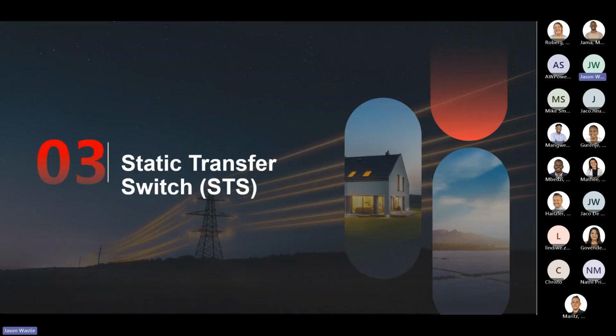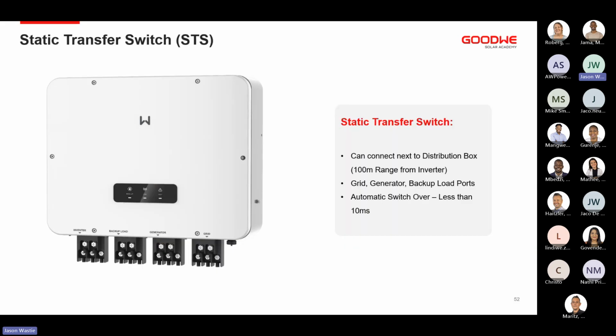So our static transfer switch, the STS, is a box that would be connected to your system between the DB and the inverter, and this is what allows you to connect your backup loads to your inverter. One of the biggest benefits of having an STS as opposed to the ports being directly connected to your inverter is that you can connect this next to your DB and up to 100 meters away from your inverter.